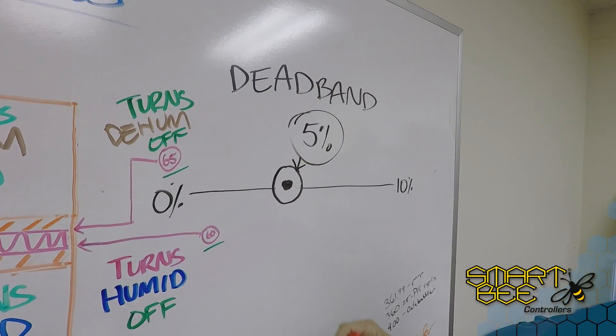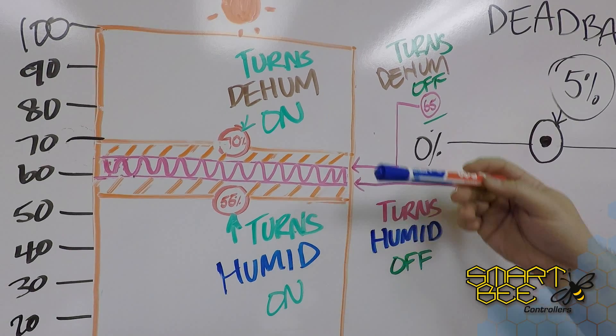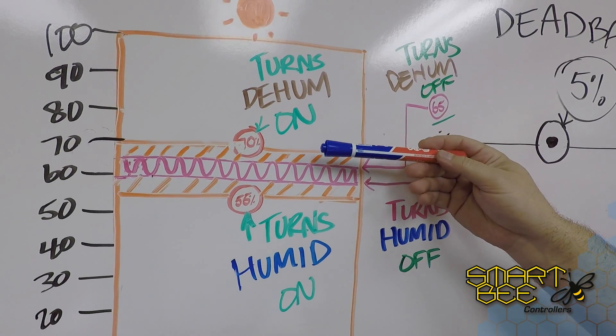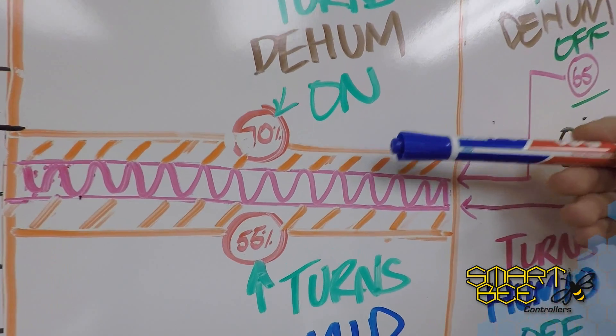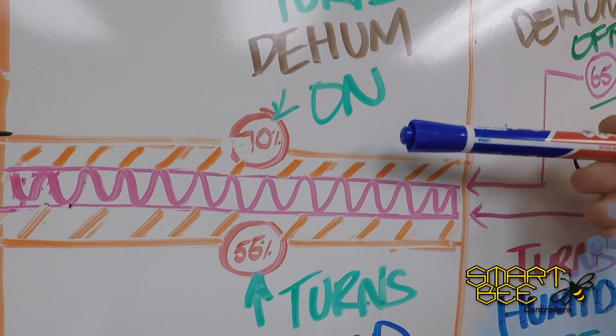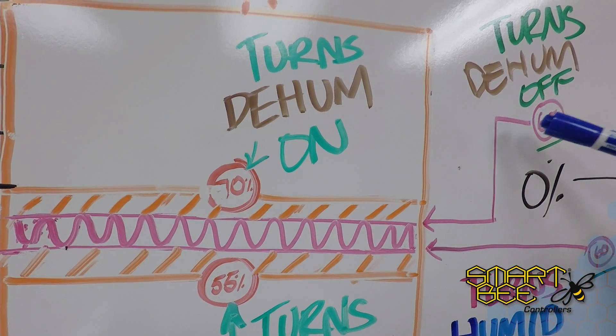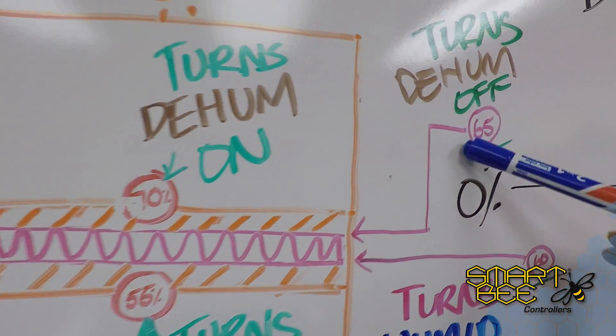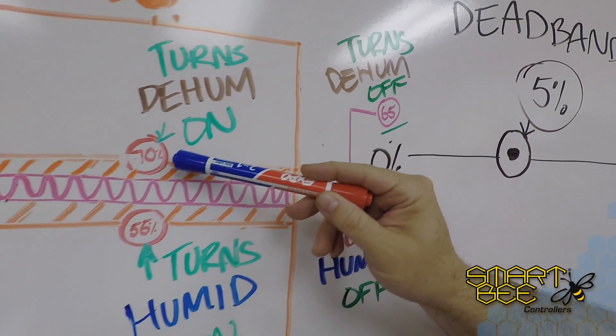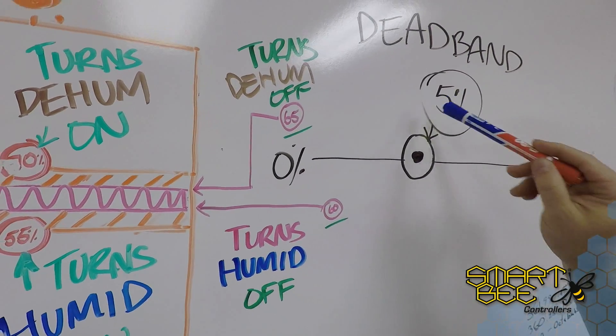What will realistically happen within your room is: in the event your humidity goes above 70 percent, the dehumidifier will kick on, but it won't kick off until it reaches 65 percent — your setting of 70 percent minus your 5 percent dead band.